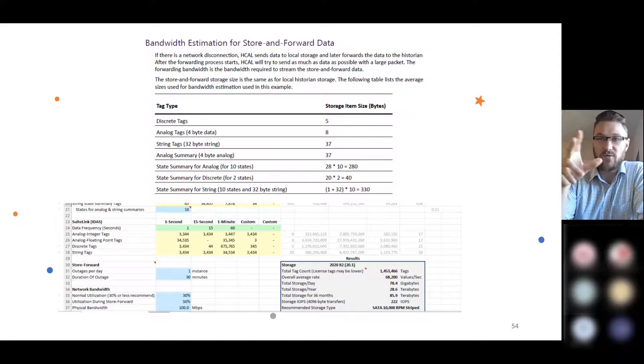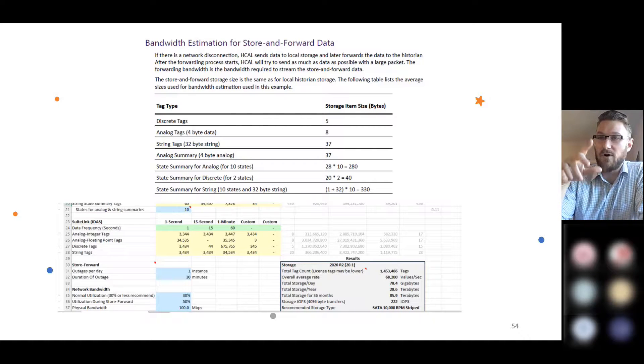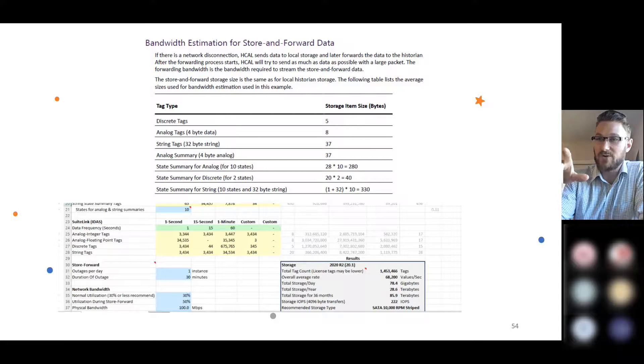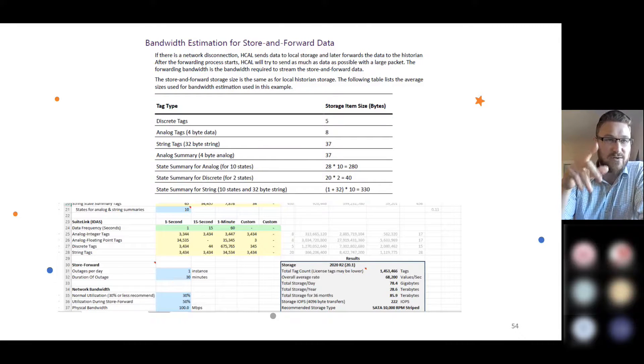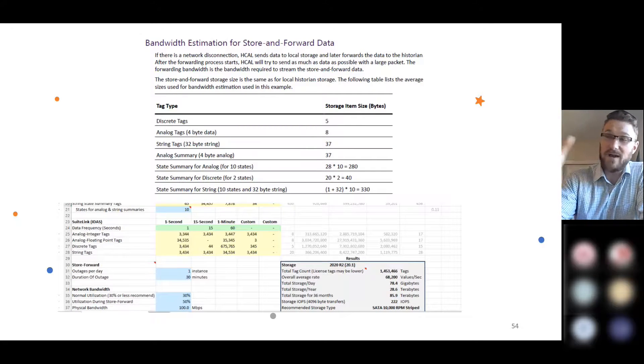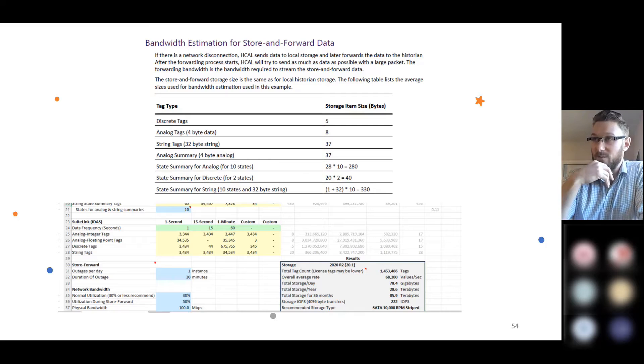At the bottom I've run some arbitrary numbers through this calculator. In the bottom right you can see for all the different tags included: total tag count — I've got around a million tags — overall rate of values stored in values per second, and total storage per day — around 80 gigabytes. In the bottom left you can see the number of outages per day I've estimated. If you've never run through this type of calculation, schedule a design review with us and we can go through these numbers with you.